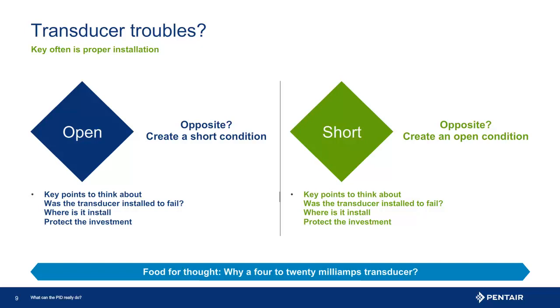Best advice: protect the investment. Understand where to properly install the transducer in the system. If installing the transducer on a metal pipe, isolate or insulate the transducer. Often a snubber can achieve this, but check with the manufacturer. Water hammer? A snubber again can protect the investment. A proper installation can mean all the difference.